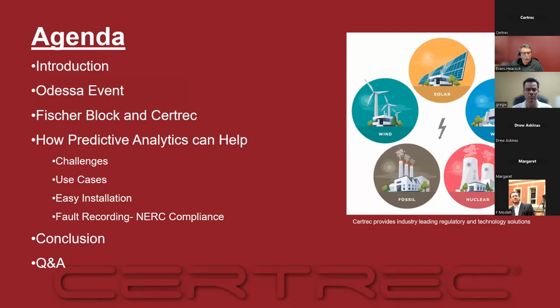What we're going to go through is a high-level background on the Odessa event that happened 2 years in a row, 2021 and 2022. We'll go over what happened and, in the end, how Fischer Block can tie into that, how Fischer Block and Certrec are working together, and how predictive analytics can help with challenges. We'll look at use cases, a number of which Greg will talk about today. It's very good about picking up most of these things. So, really, it's a neat device. You can't beat what it's doing from predictive analytics, along with the ease of installation. Then we'll talk about fault recording for NERC compliance, and we'll go through conclusions and questions and answers at the last.